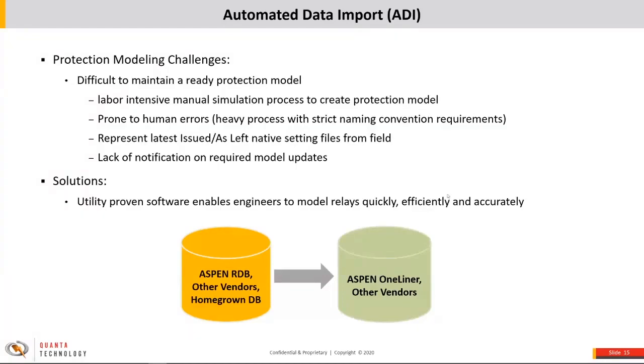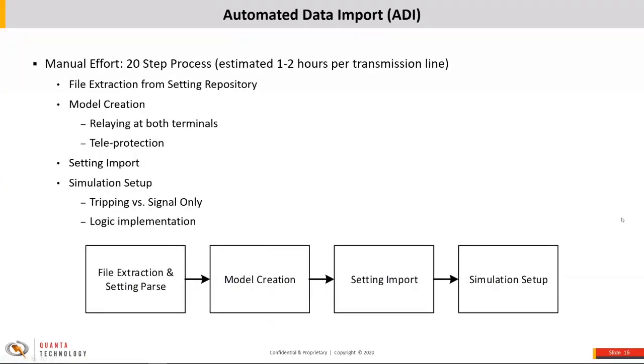The first use case addresses the challenges in protection modeling. As Sam mentioned, it's difficult to maintain a study-ready protection model. Common challenges among utilities include a labor-intensive manual process to create protection models in the short-circuit model, ease of human error, and different statuses of settings you may want pushed into the model at different stages. We have an automated solution called ADI — Automatic Data Import — that allows you to connect to your relay repository and automatically push the settings and create the models in short-circuit software such as ASPEN OneLiner.